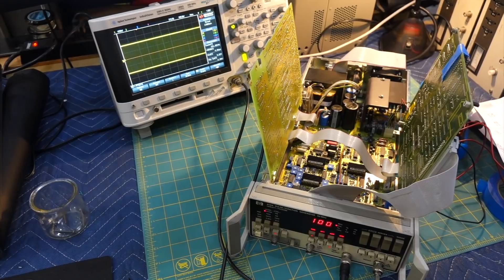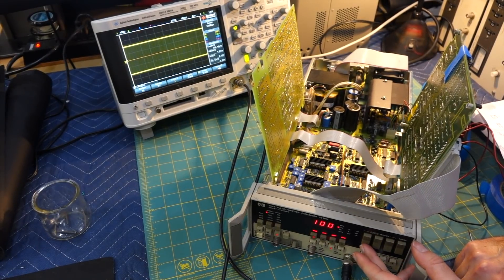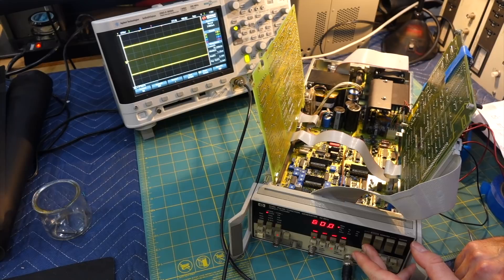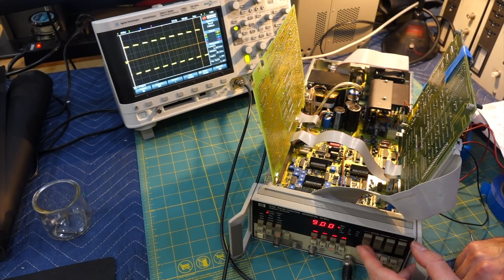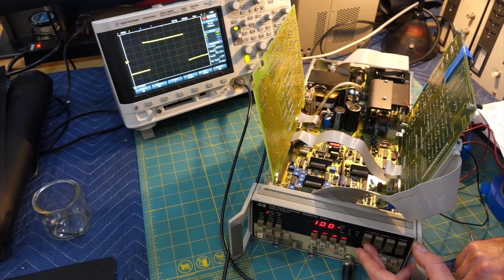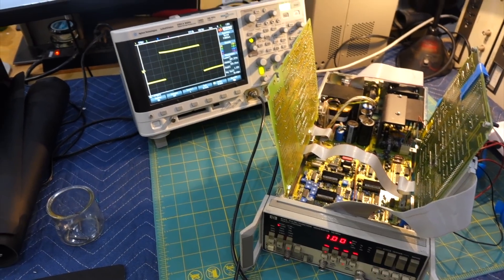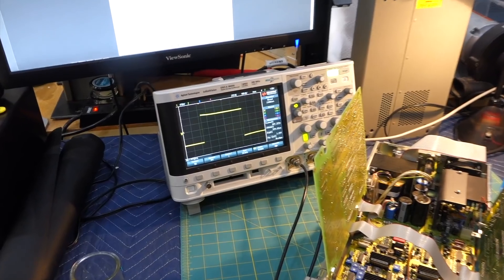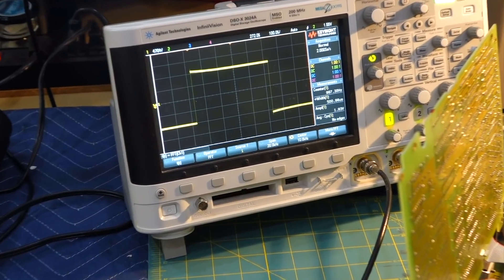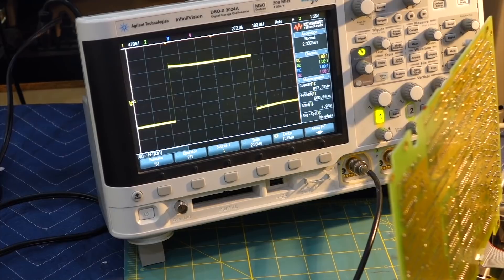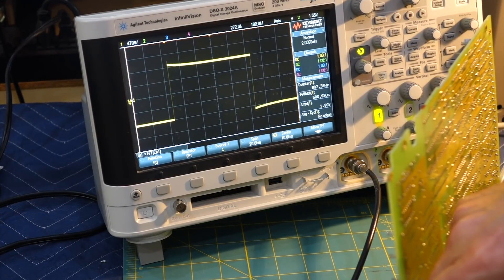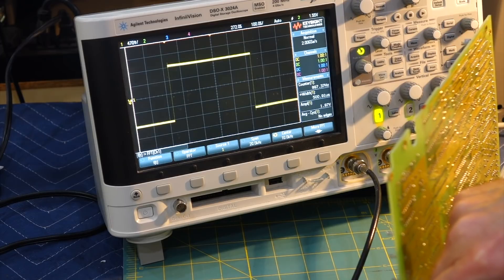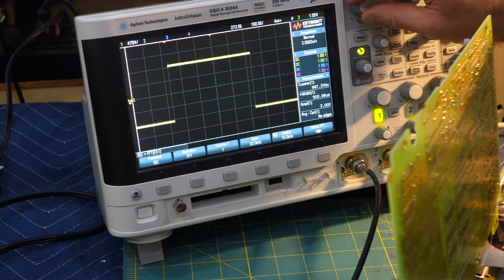So once you're done with all your amplitude and offset adjustments, then you have to go down to another setting that was way off. You have to go down to 1 kHz, and make that beautiful thing look nice and flat. That's the low frequency adjustment pot. Something like that.